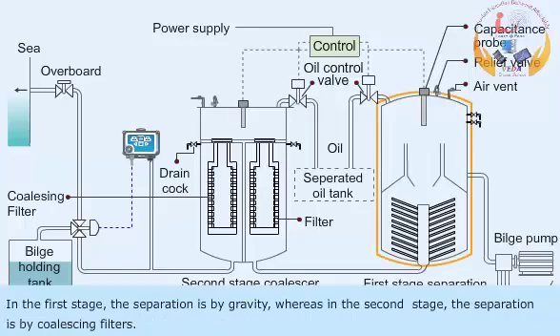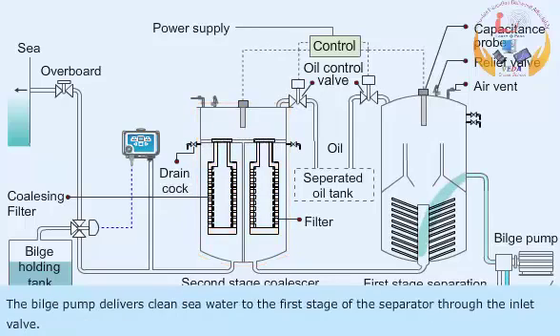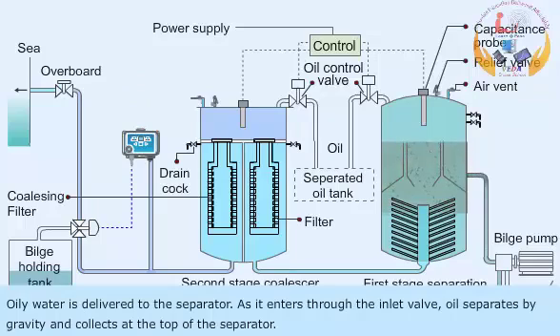In the first stage, the separation is by gravity, whereas in the second stage, the separation is by coalescing filters. The bilge pump delivers clean sea water to the first stage of the separator through the inlet valve. The vent is kept open until all the air is removed from the separator and water issues out. Oily water is then delivered to the separator, and as it enters through the inlet valve, oil separates by gravity and collects at the top of the separator.